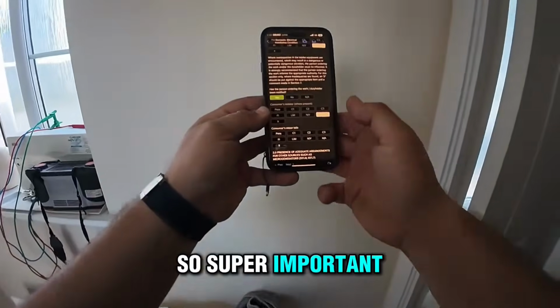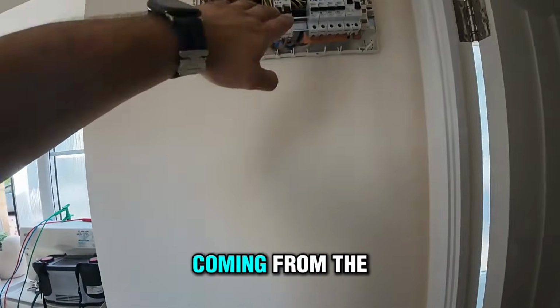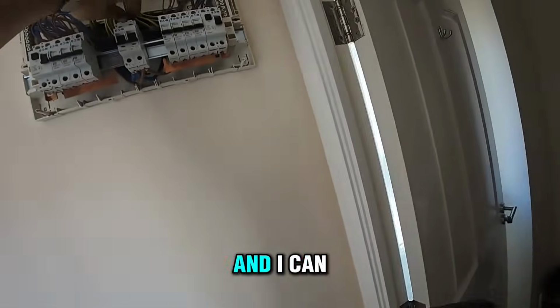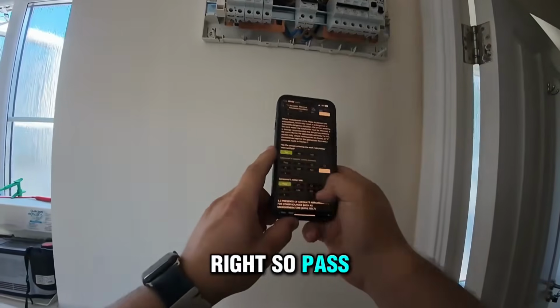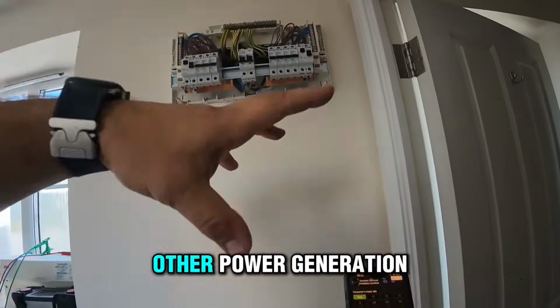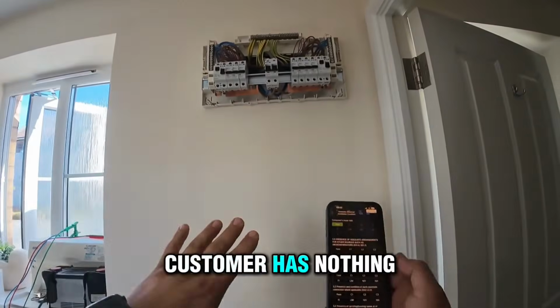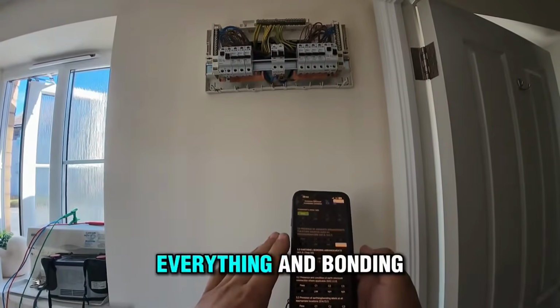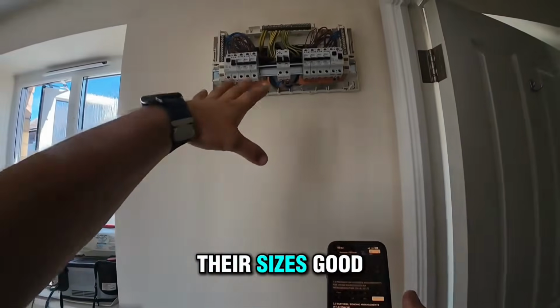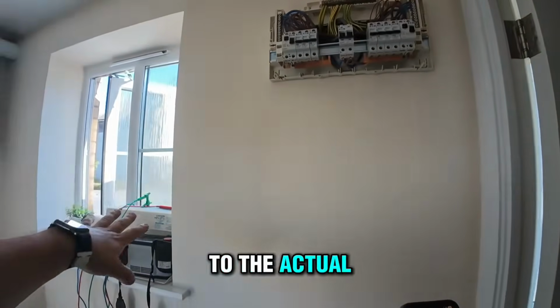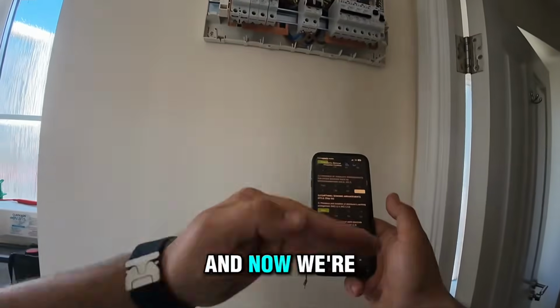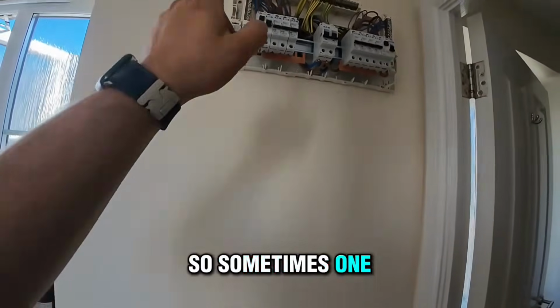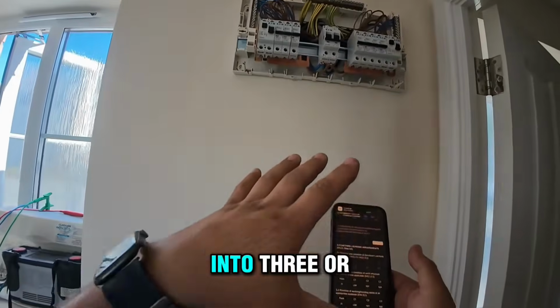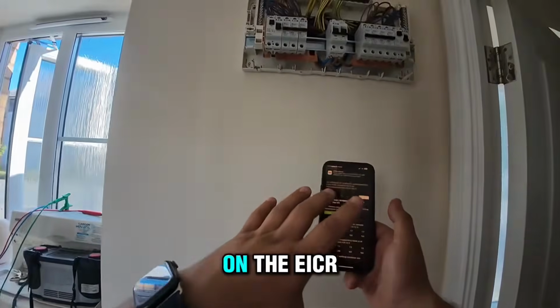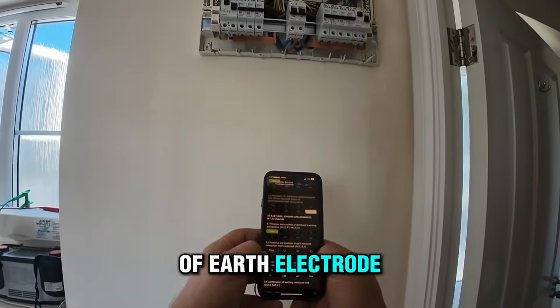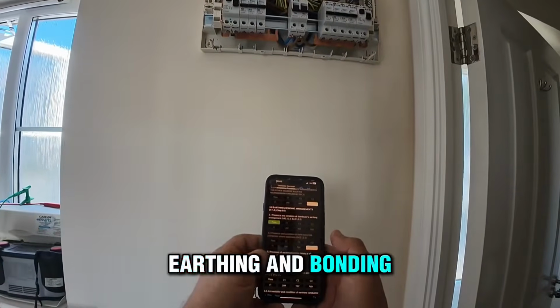There is no consumer isolation. So, super important. Consumer meter tails. These are the ones coming from the meter into here, and I can see that they're absolutely fine. Right, so pass to this. For PV or any other power generation systems, the customer has nothing like this in this property. Earthing and bonding arrangements. We've checked their size is good. We've checked continuity to the actual gas, security of fixings, and now we're just being asked about it. Sometimes one problem could relate to 3 or 4 failed regulations on the EICR. Presence and condition of earth electrode, we don't have one. Provision of earthing and bonding labels, yes.